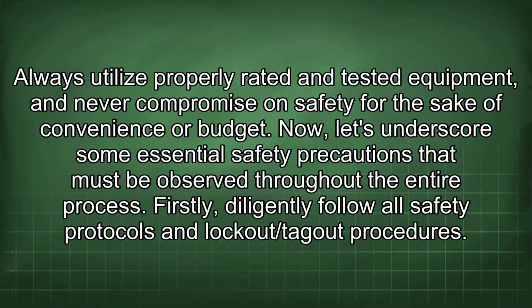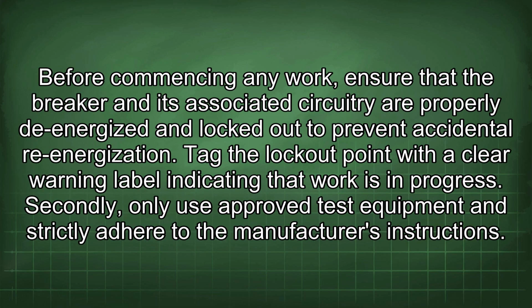Firstly, diligently follow all safety protocols and lockout/tagout procedures. Before commencing any work, ensure that the breaker and its associated circuitry are properly de-energized and locked out to prevent accidental re-energization. Tag the lockout point with a clear warning label indicating that work is in progress.